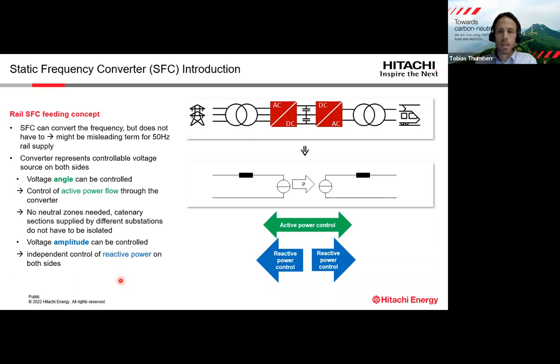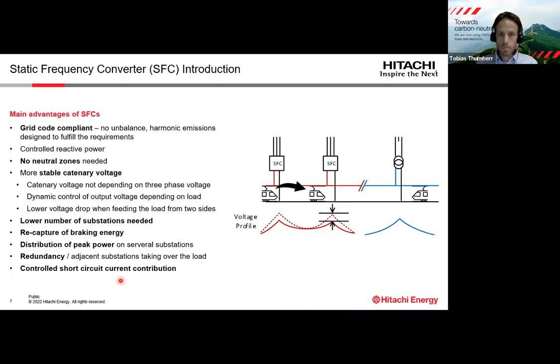We can operate these feeding substations with SFCs in parallel, and you can have a whole railway line that is not isolated between the different sections. The second thing that can be controlled with this controlled voltage source is the amplitude of the voltage, and with this we have independent control of reactive power on both sides. I think there are many advantages of rail SFCs compared to conventional substations with transformers. I want to go into the main ones here, and I think we can summarize them under two things. One of them is grid code compliance, and the second one is increased flexibility in designing and operating the railway power supply.